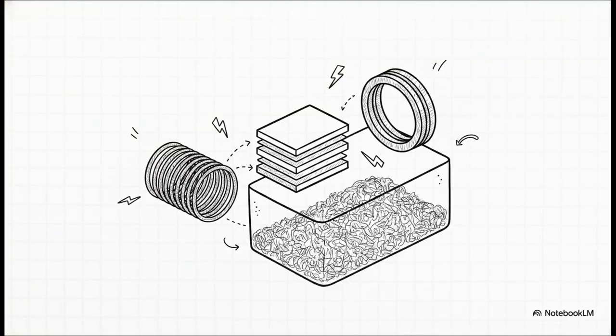So how does it actually pull off this translation without being blown to pieces itself? Well, a potential transformer isn't just some random hunk of metal. It's an absolute masterclass in precision engineering, built from the inside out with 4 core components. First up, the core. This is made of high-grade silicon steel laminations. And why laminations, you might ask? Because they reduce what engineers call eddy current losses. Basically, we want the energy transferring efficiently across the device rather than just turning into useless, damaging heat.